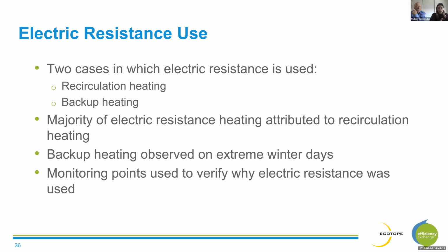One is due to recirculation losses, and this just means when tenants aren't using very much hot water, the water that's circulating the building begins to cool, and so our swing tank will turn on and heat that water back up to set point. The second situation is in extreme cases, the electric resistance system can be used for backup heating. This would occur if we were to completely deplete our hot water storage tanks and the heat pump was not able to handle the load on its own.